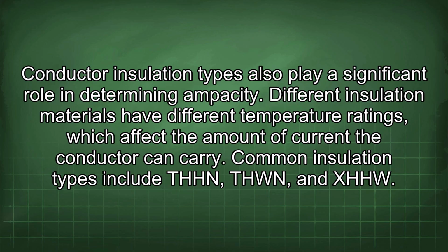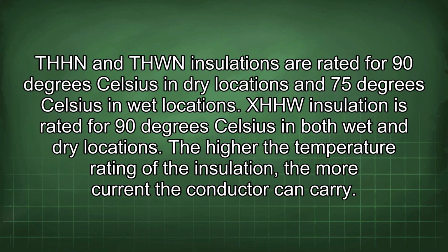Conductor insulation types also play a significant role in determining ampacity. Different insulation materials have different temperature ratings, which affect the amount of current the conductor can carry. Common insulation types include THHN, THWN, and XHHW. THHN and THWN insulations are rated for 90 degrees Celsius in dry locations and 75 degrees Celsius in wet locations. XHHW insulation is rated for 90 degrees Celsius in both wet and dry locations. The higher the temperature rating of the insulation, the more current the conductor can carry.